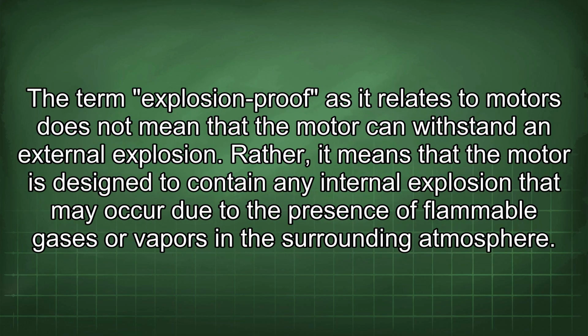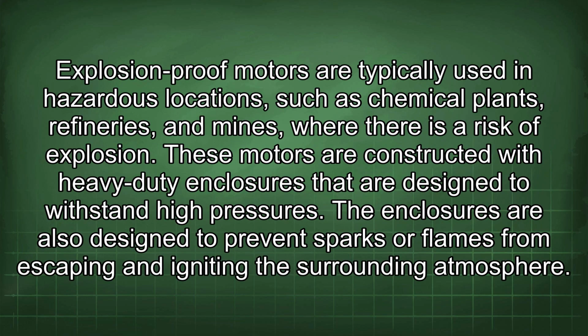The term explosion-proof as it relates to motors does not mean that the motor can withstand an external explosion. Rather, it means that the motor is designed to contain any internal explosion that may occur due to the presence of flammable gases or vapors in the surrounding atmosphere. Explosion-proof motors are typically used in hazardous locations such as chemical plants, refineries, and mines, where there is a risk of explosion. These motors are constructed with heavy-duty enclosures that are designed to withstand high pressures. The enclosures are also designed to prevent sparks or flames from escaping and igniting the surrounding atmosphere.